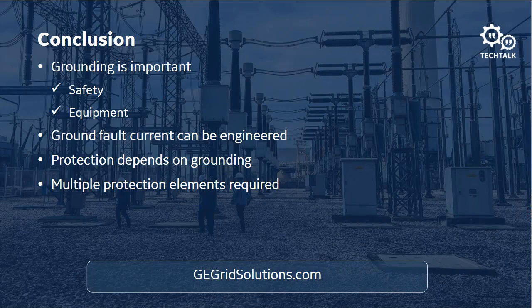It might be subject to where it will not be able to detect certain types of ground faults, especially if the generator is operating in a low pocket where we have low third harmonic voltage. So if we have low third harmonic voltage, the voltage differential, depending on the pickup setting, might not be able to pick up for a ground fault in that region. So it's more secure than the 27 TN, but it's not completely dependable.